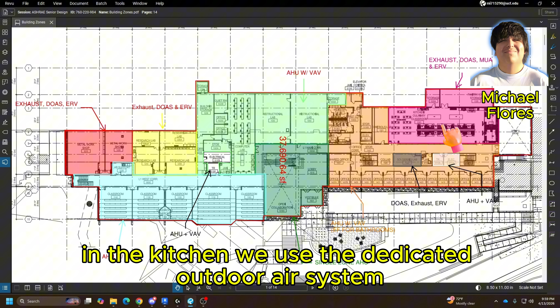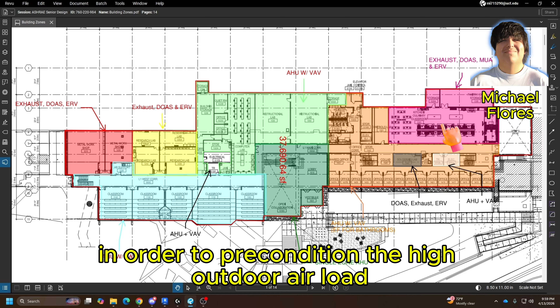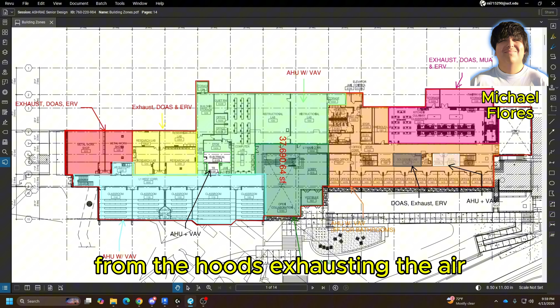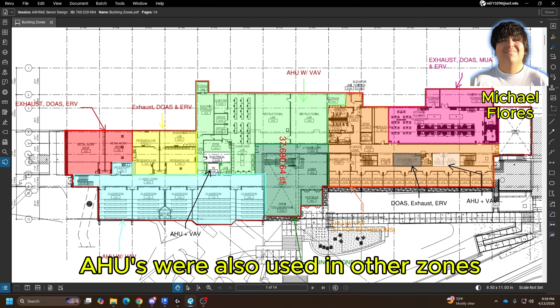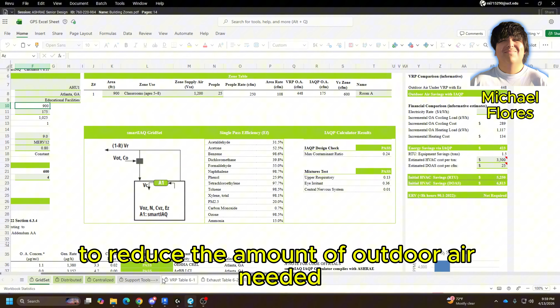We use different systems throughout the building. In the kitchen, we use the dedicated outdoor air system, or DOAS, in order to precondition the high outdoor air load. Makeup air units were used to balance the kitchen's air pressure from the hoods exhausting the air. And an air handling unit, or AHU, was used for thermal comfort. AHUs were also used in other zones to provide conditioned air into them. Bipolar ionization was used to reduce the amount of outdoor air needed in different zones following the ASHRAE 62.1 IAQ method. This leads to less energy being used to condition the outdoor air.